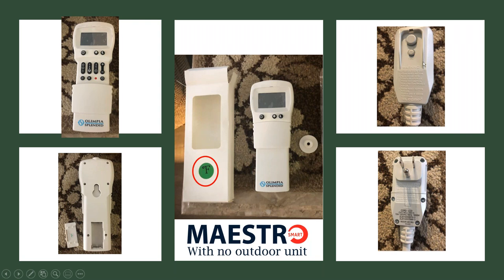So it's designed to shut the unit down if there's overcurrent or any impact on the overall circuit. If you look at the installation instructions, it will tell you the factory recommends a dedicated circuit for the unit. It does not say you must use a dedicated circuit. It simply recommends it. So what that means is if you have a dedicated 15 amp circuit, for instance, and this is the only thing on there, you're not going to come close to tripping a breaker, right? But if you plug this into a wall outlet, and unbeknownst to you, they also have two refrigerators on that same circuit, well, something's going to give. That circuit breaker or that GFI is going to trip.